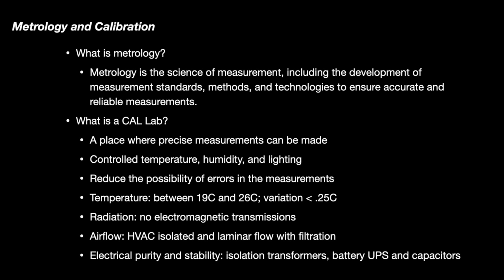But also, the quality of the electricity that's being used within the calibration laboratory to power the instruments is important. You want it to be as clean as possible, no noise on it. So if you've got a 5 kilowatt generator down the hall, or a big electric motor that's starting and stopping, probably not a good idea to be on the same circuit as that with the electronic instruments.